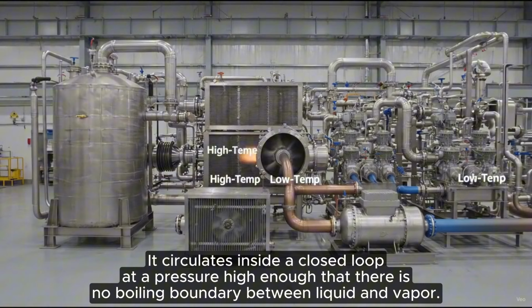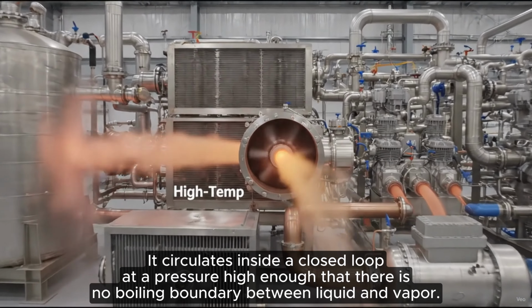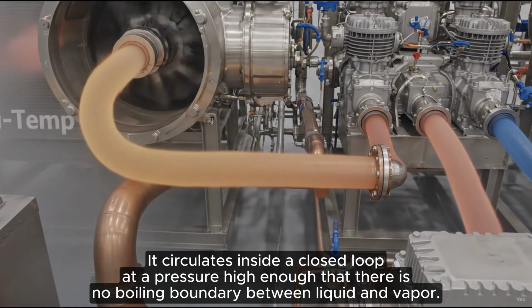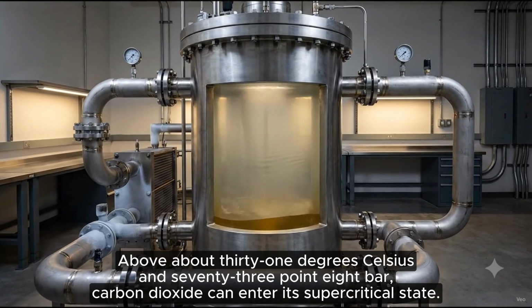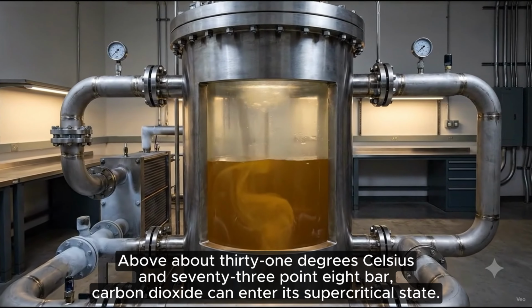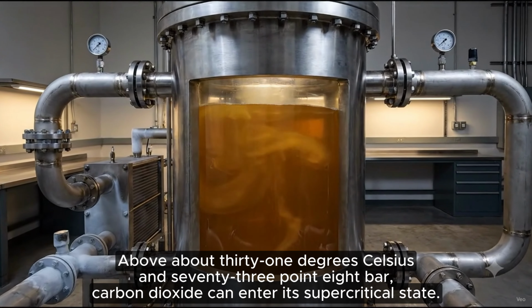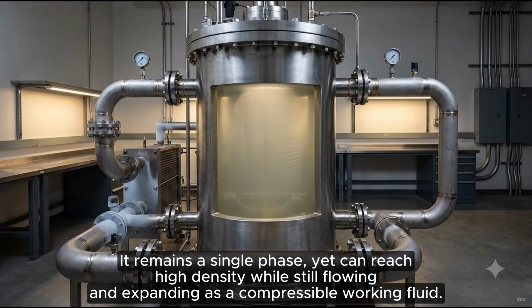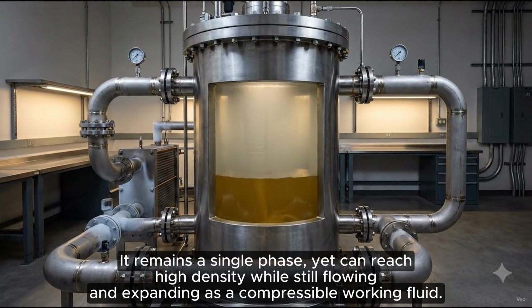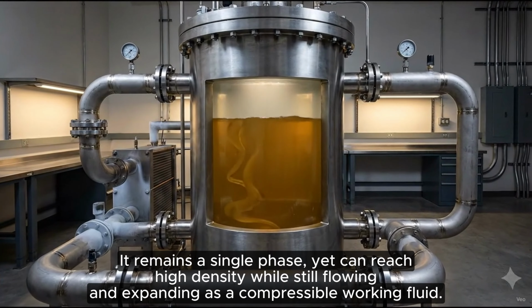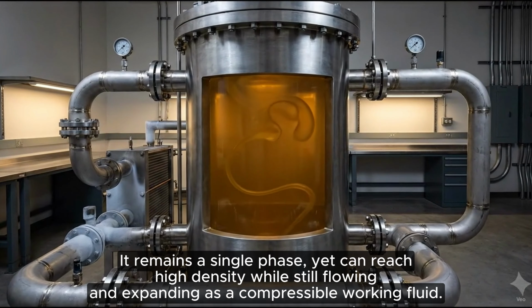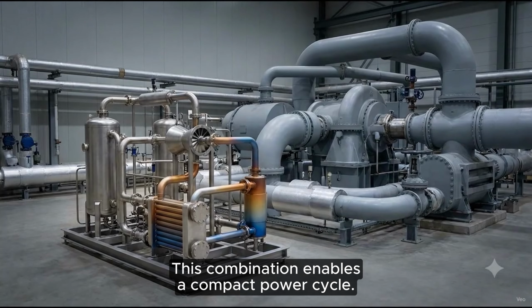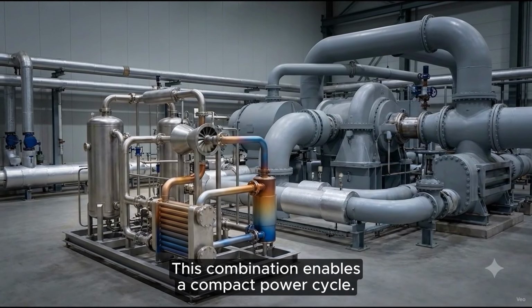It circulates inside a closed loop at a pressure high enough that there is no boiling boundary between liquid and vapor. Above about 31 degrees Celsius and 73.8 bar, carbon dioxide can enter its supercritical state. It remains a single phase, yet can reach high density while still flowing and expanding as a compressible working fluid. This combination enables a compact power cycle.